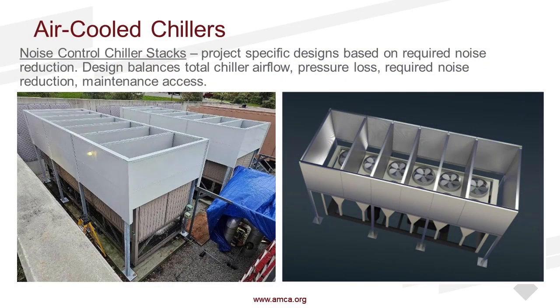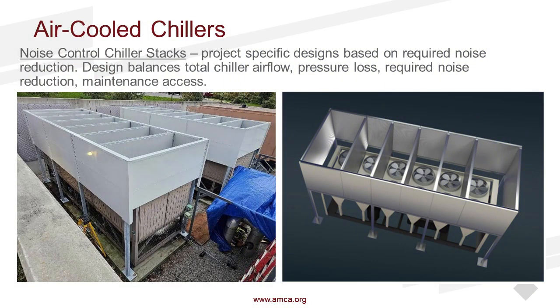One option right here is for a chiller stack. If you look at this, these are all perforated inner shells. So these separating baffles, which go completely between, they don't obstruct the fans. They're stacked, simply supported external to the air-cooled chiller. And the air, you pair off each fan. These are perforated inner shells, and each of these baffles are perforated both sides. And then this is a solid outer shell. So it's basically an insulated stack that's going to control the noise.